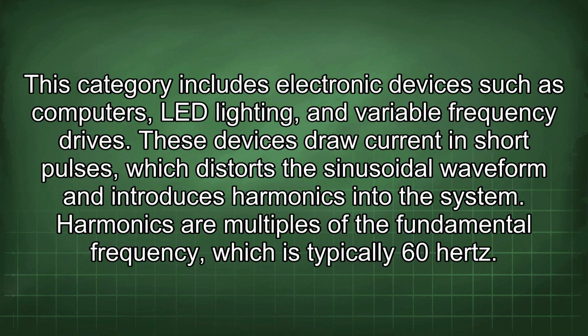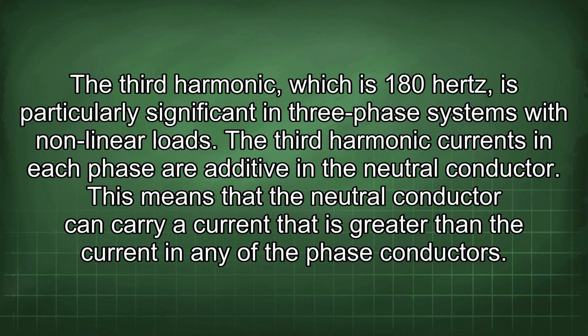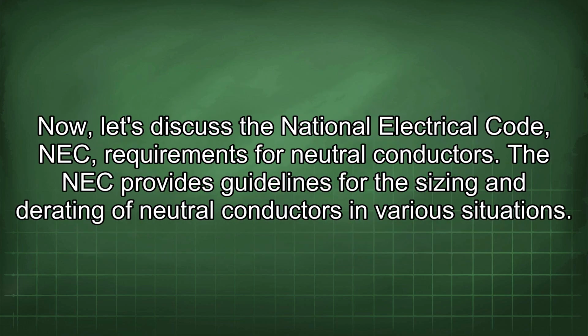Harmonics are multiples of the fundamental frequency, which is typically 60 Hz. The third harmonic, which is 180 Hz, is particularly significant in three-phase systems with nonlinear loads. The third harmonic currents in each phase are additive in the neutral conductor. This means that the neutral conductor can carry a current that is greater than the current in any of the phase conductors. Now let's discuss the National Electrical Code (NEC) requirements for neutral conductors. The NEC provides guidelines for the sizing and derating of neutral conductors in various situations.